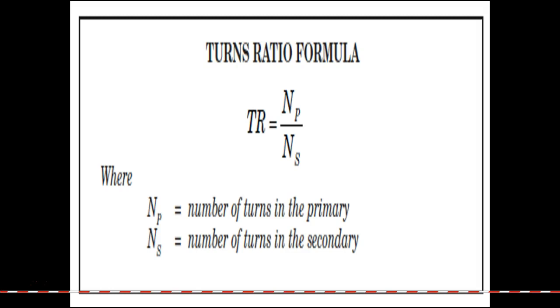If you short out a winding, you change your turns ratio. So most of the time, if you're not getting as much voltage out as you want, odds are windings inside either the primary or secondary are shorted together. They short together, you change your turns ratio, and there's really nothing you can do about it - you just buy new and throw the old one away.